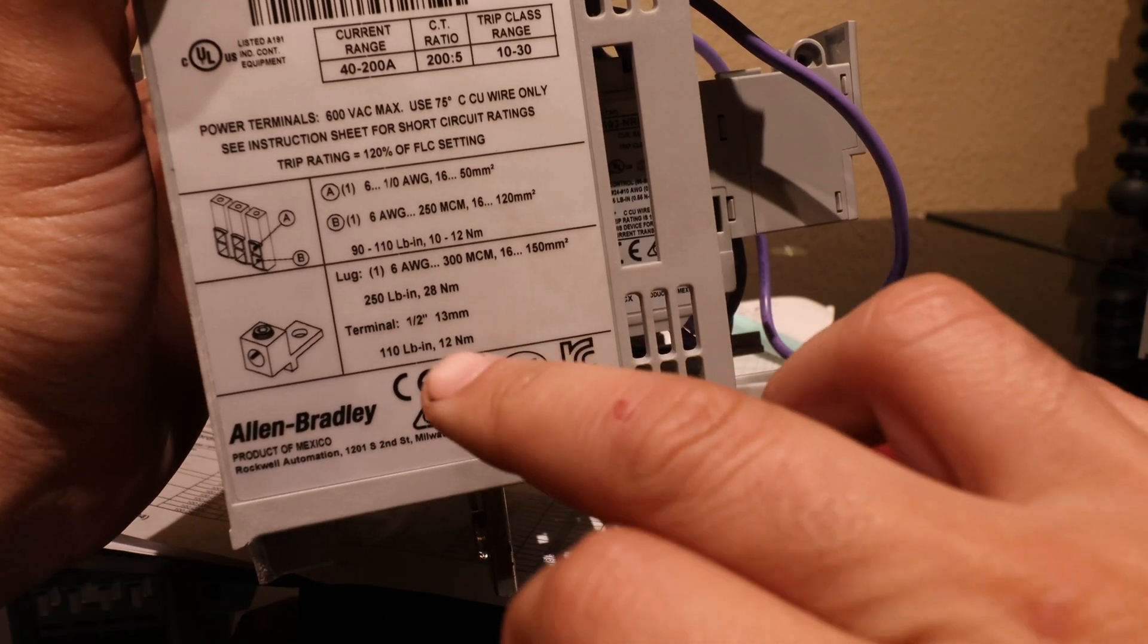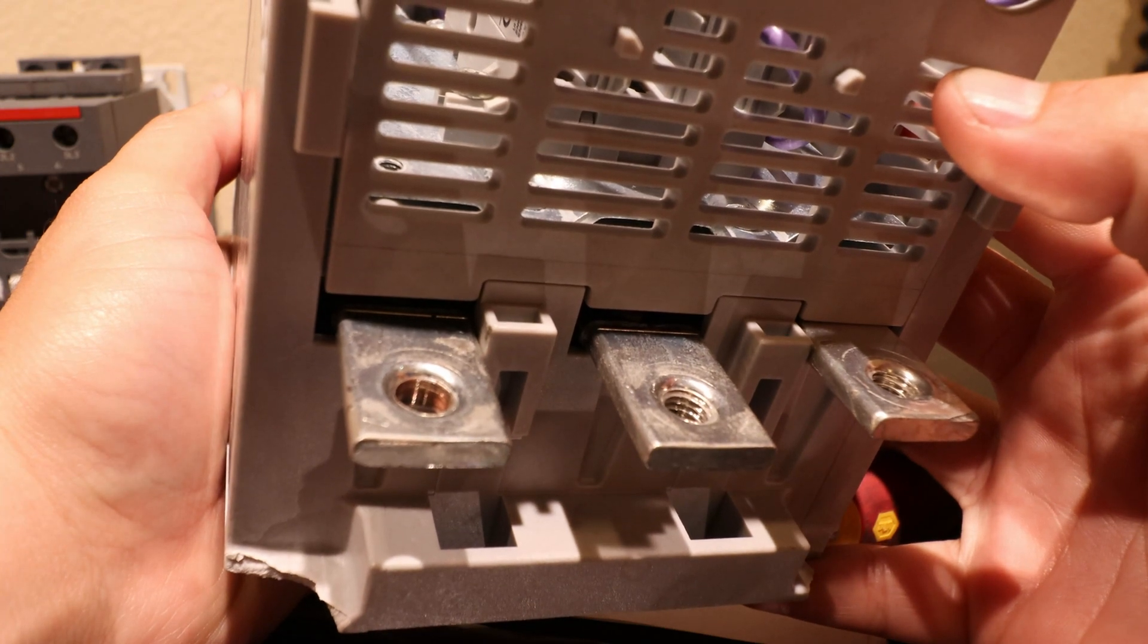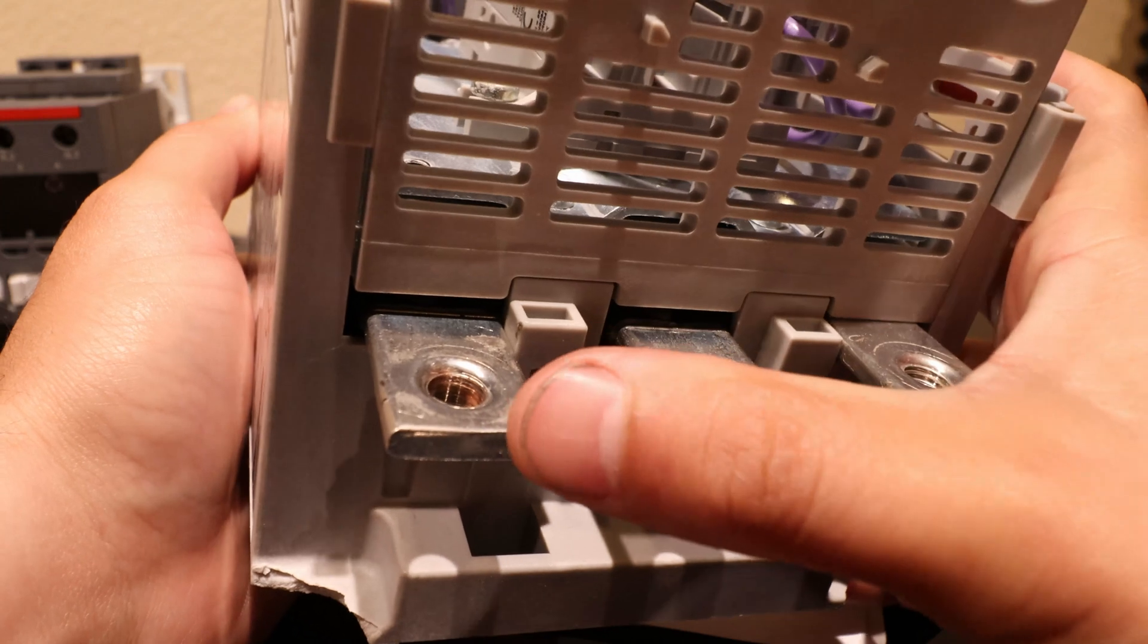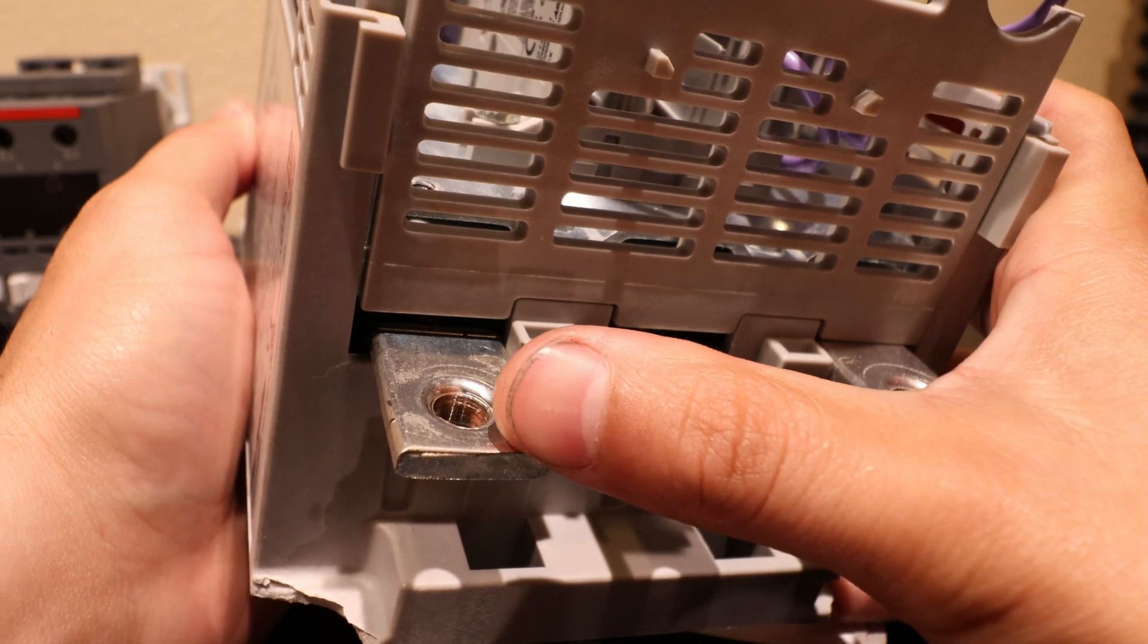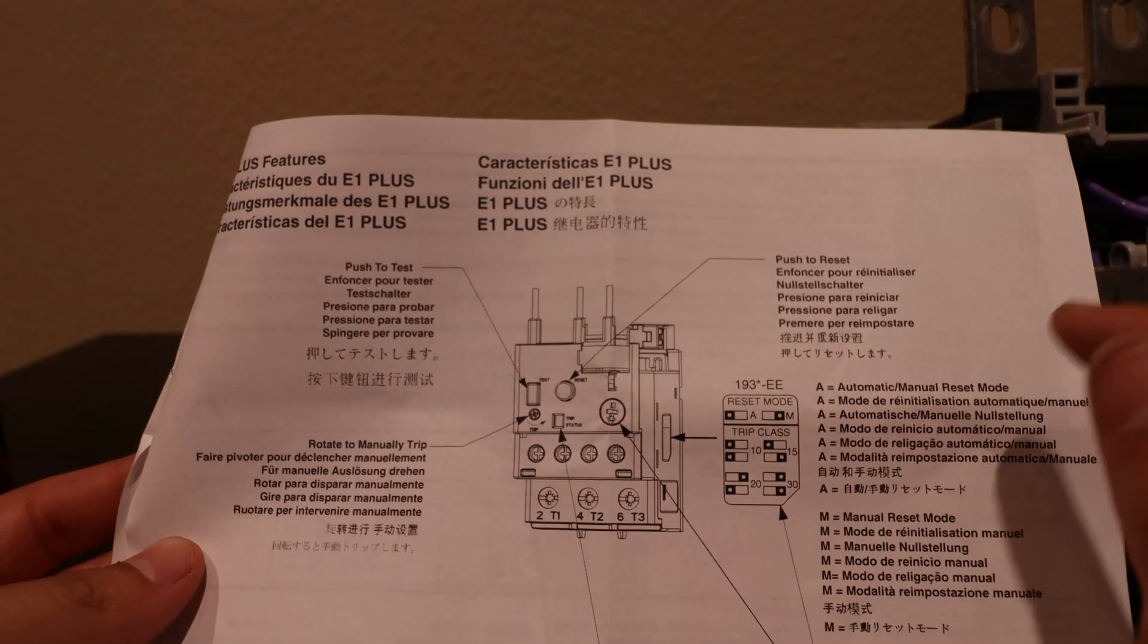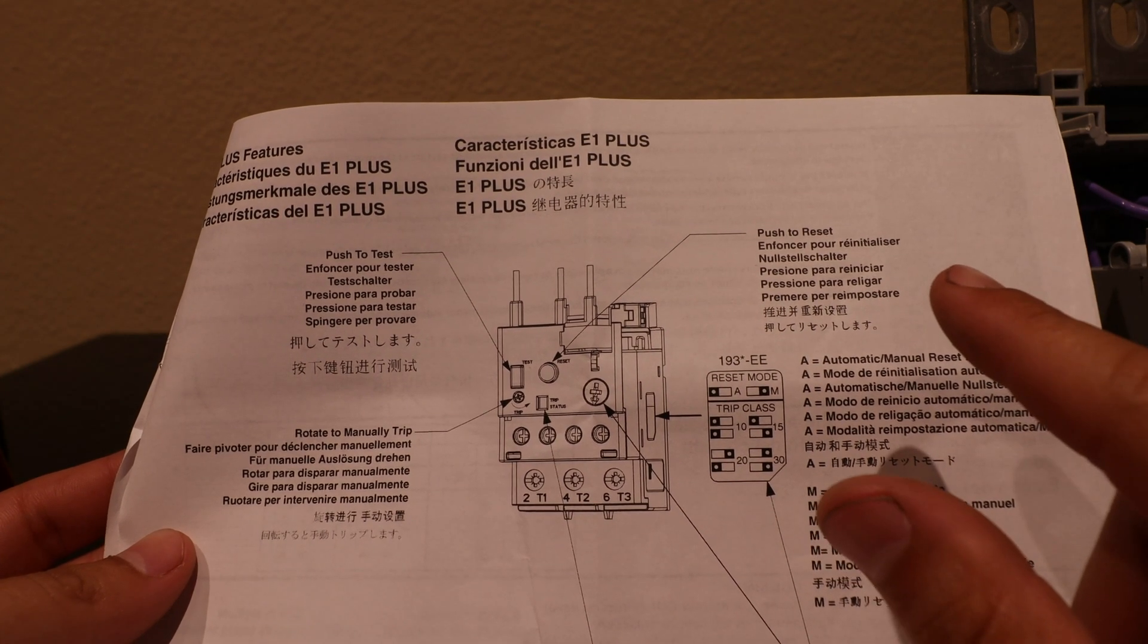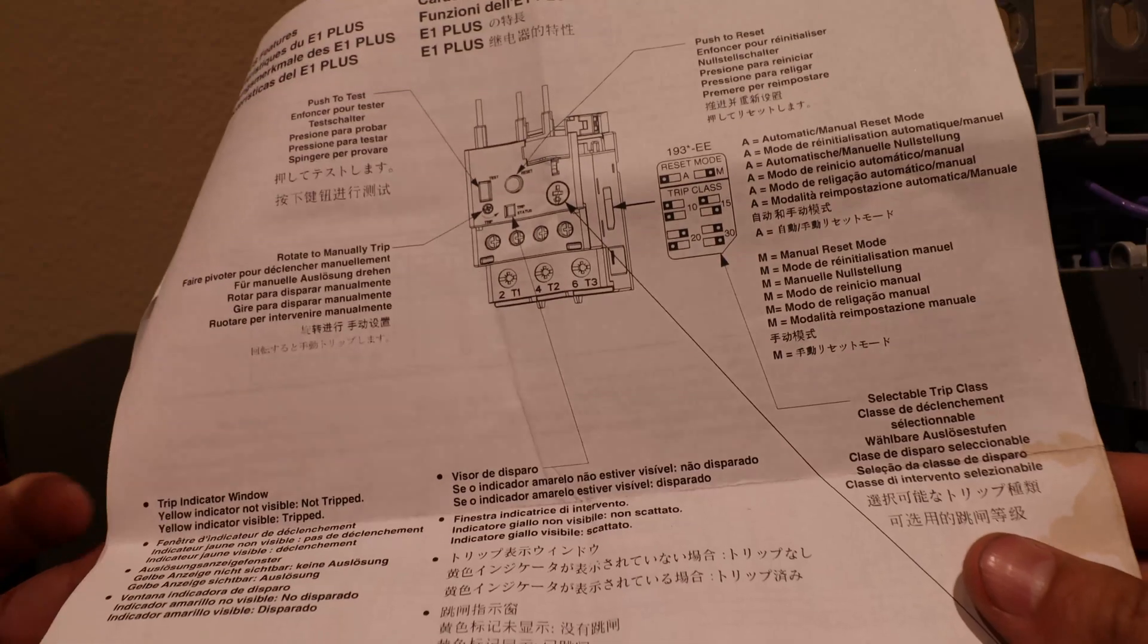It's also worth mentioning you should pay attention to the tightening recommendations used on these bars. As you can see these threaded bars on the bottom, this one's still good but the one on the left has been stripped out. See that copper color in there? Well it's actually copper. This is a copper bar and it's plated with something else, and copper is really soft so it's pretty easy to strip these out. In your manual that came with the overload relay it mentions what the buttons do. I'm going to tell you what my old VP used to tell me, VP of service department - RTFM. If you ever got a question about anything, just get the manual and read it. You read English, it's in English, just read it.